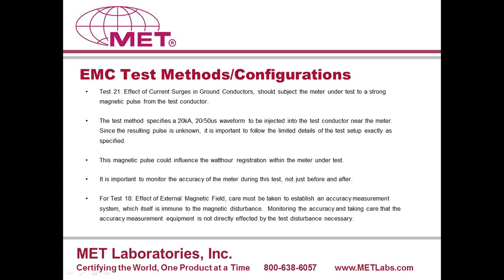The next test is test number 18, effect of external magnetic field. Now, this test is done where the meter is subjected to an external magnetic field of 100 ampere turns, and the meter is placed at a distance of 10 inches from the center conductor of the coil that is producing this magnetic field. So the way this test is done is you create a field of 100 ampere turns, place the meter about 10 inches from the center conductor of the coil in various orientations, X, Y, and Z, and then you monitor the meter for any change in the performance when it is subjected to this external field.